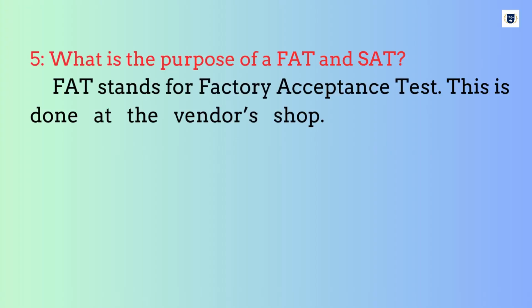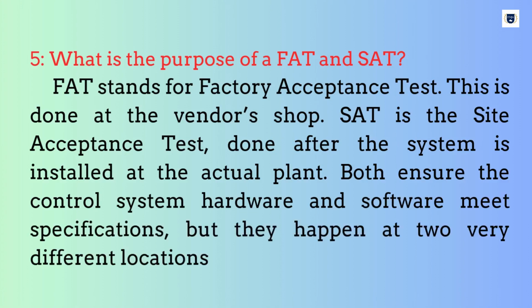What is the purpose of a FAT and SAT? FAT stands for Factory Acceptance Test. This is done at the vendor's shop. SAT is the Site Acceptance Test, done after the system is installed at the actual plant. Both ensure the control system hardware and software meet specifications, but they happen at two very different locations.